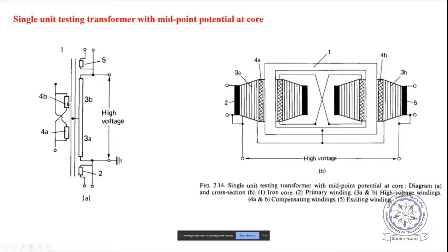So what will happen? As you can see here, from this point to this point is considered high voltage. At the midpoint it is connected to the core, but the core is not at ground potential. This point is at ground potential, and the primary, secondary, and tertiary or excitation winding are here. So this is the main high voltage winding, and these two windings are the compensating windings.